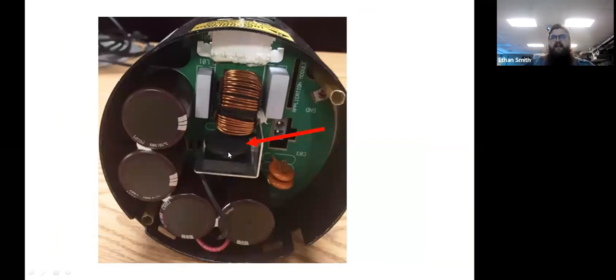These resistors are non-replaceable items. I know that you can go out on Alibaba and buy them. I do not recommend that you install them. These are a safety device. If you take this out and defeat it, or take the 2 stubs of bare wire and twist them together, you're defeating a safety device. So if this resistor has failed, A, you need a new power head, and B, you need to find out why it failed. Go start taking some static pressure tests, look at the ductwork. It could simply be that the guy only changes his filter every year, or every 6 months. Maybe have a conversation about getting them on a maintenance agreement so that happens more often. Otherwise, you're just going to be back, or somebody else is going to be back, and your homeowner is going to badmouth you to the next guy. Yeah, this thing failed 3 years ago. I had it replaced. Dead again. You know how the story goes. But that current limiting resistor dies because of high static situations.